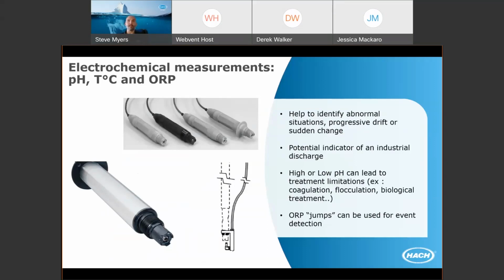So keeping an eye on pH - it's not surprising that many, if not most, plants out there already have this. ORP is also a relatively interesting parameter for monitoring. It can illustrate anaerobic conditions, or if an industry is discharging oxidants - maybe something coming down the line that could kill bacteria, and we can pick that up with ORP as an event detector, or it could be a slow increase over time, like a trend line. These can be helpful tools for monitoring your influent.